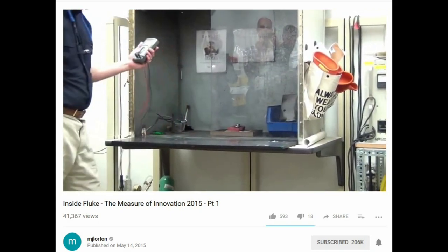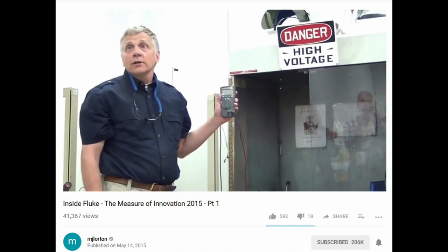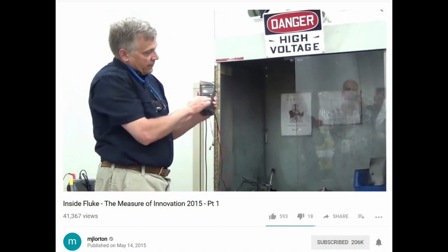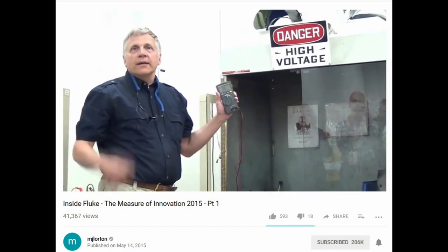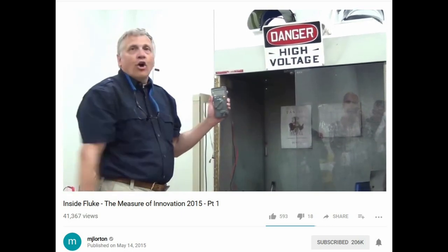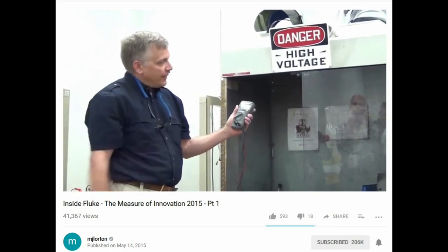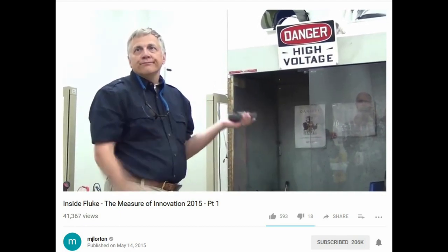So this meter is a 600 volt category 2. So I'm putting again 660 volts into it. And go to the voltage setting and it shows overload. That's because I'm putting in greater than the rated voltage into it. And if I put it into ohms, which I just did to that meter, there's no issue.